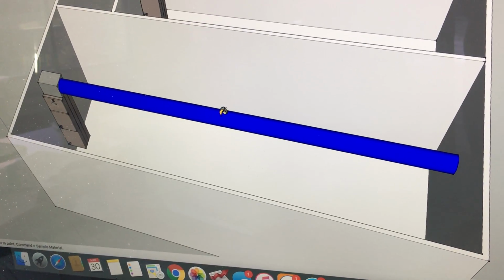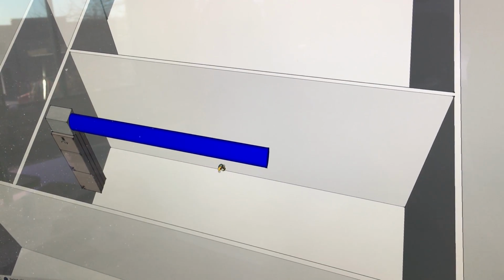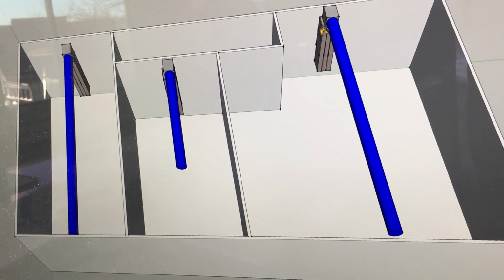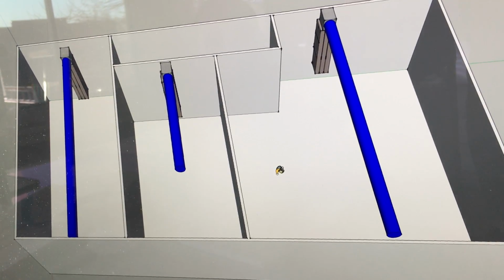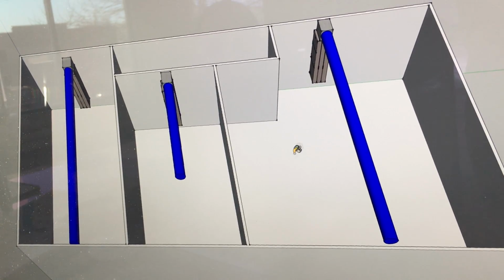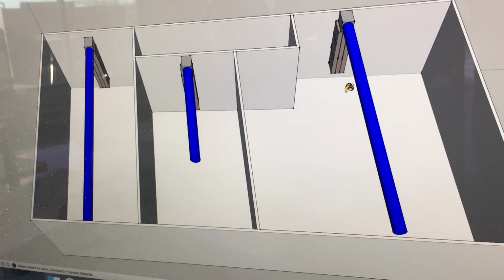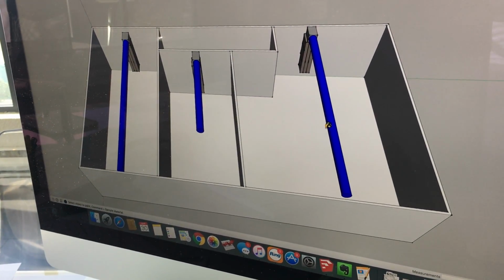So it's actually two kits of fabric ducting versus, as you can see here, with just one kit for the veg room. And so the other room here is the other bloom room. Same concept, we ran 30 feet of ductwork off of it. And this guy now has the ability to cool 45,000 watts with the 3 5-ton Elites and have exact humidity control as well. So give us a call, we can do a drawing anytime for you.